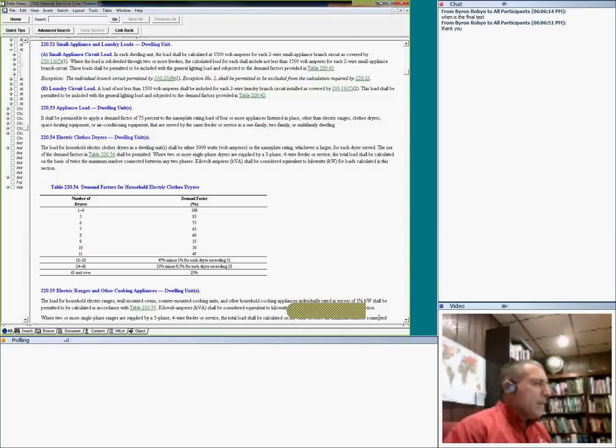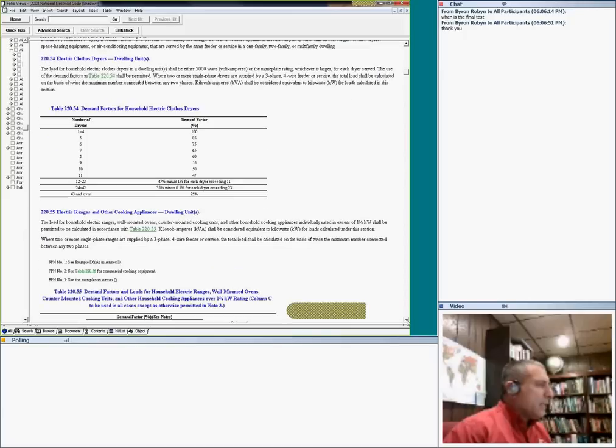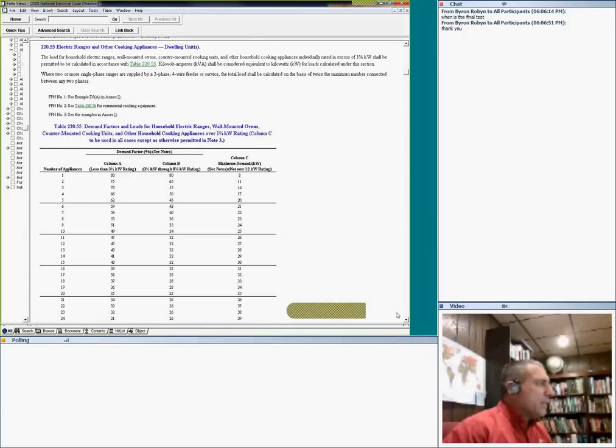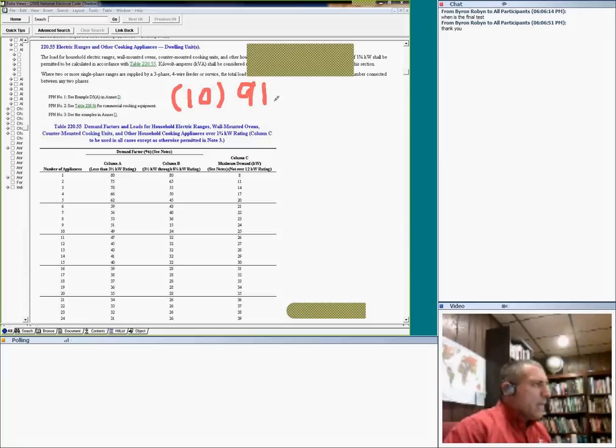Moving on to the electric range. Here's how the range calculation works, without getting into too much detail. Let's just make it very simple. Suppose you have 10 ranges, each one of these ranges is 9 kW, which is equivalent to kVA. So 10 of them. Since they are 9, they are more than A, more than B, so they are definitely under C. So the demand factor for 10 of them, guys, is 25.